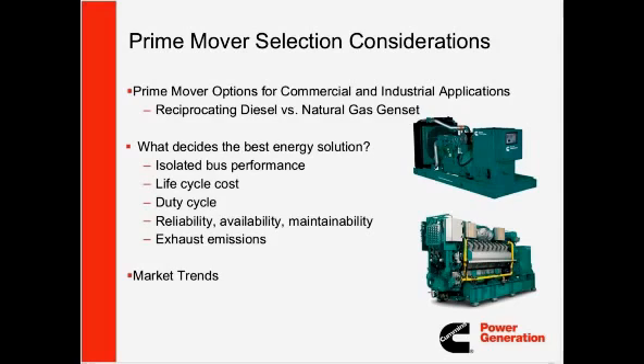And when we talk about isolated bus performance, for those who are not power systems engineers, we're mainly talking about a situation where a generator or a group of generators are feeding the load, not running in parallel with the utility grid, where frequency stability is important. The other thing we're going to have to consider is the life cycle cost. Life expectancy of diesel and natural gas generators are different. How often do you need to maintain it, and the capital and operational costs are different, so we have to consider that when selecting the fuel type for the prime mover.